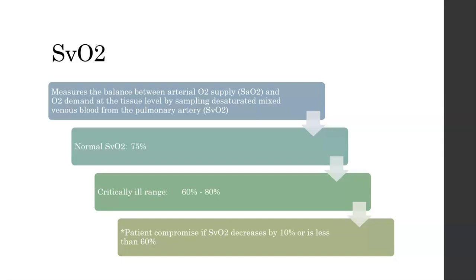Oxygen is taken up in the lungs and then delivered to tissues by hemoglobin molecules in our blood. Some of our PA catheters have the ability to monitor continuous SvO2. I think St. Bernard's does, if I remember correctly, unless they've changed since I worked there. The catheter uses a light emitting fiber optic to illuminate the blood in the pulmonary artery, and another fiber optic receiver absorbs the reflected light. The hemoglobin in the RBCs reflects the light according to its saturation.